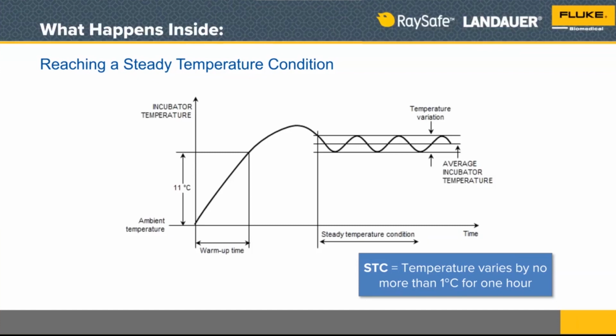The graph that we show in the slide is a visual of what's going on when an incubator is first turned on and a temperature is set, say, at 36 degrees C. So let's take a look at that. There's a warm-up time here too that we'll get to. The temperature is mapped over time, and it looks the way you see on the graph.